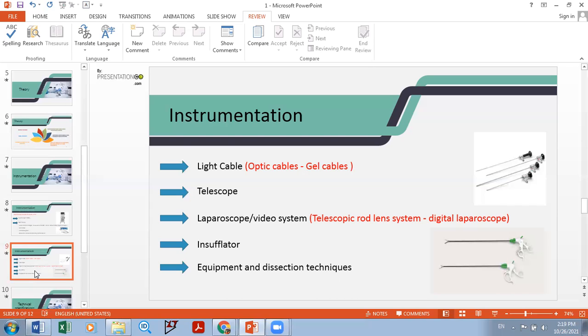The next part is the telescope, which is inserted into the abdominal wall of the patient. There are several types depending on the task. The main structure of the telescope varies in diameter from 3, 6, to 8 mm, with viewing angles of 0, 30, 70, and 120 degrees. The other part is the video system — you can use a telescopic or digital laparoscope system. The difference lies in the use of lenses, as the digital laparoscope places the camera at the end of the telescope.